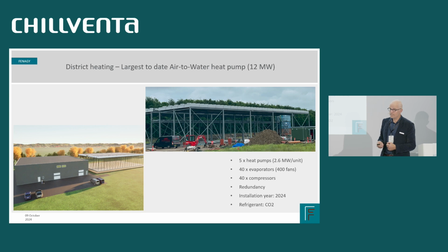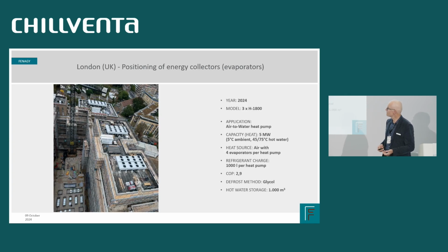And so far, our biggest heat pump is 11 megawatt. We are doing another 16 megawatt very soon. So they can be rather big, the air source heat pumps. Sometimes space is limiting because we're in a city. You would normally think that is the gas cooler, the condenser on that roof, but it is actually the evaporator. It's the energy collector collecting heat from the air for the district heating network surrounding these buildings. It's in the London area, this one.